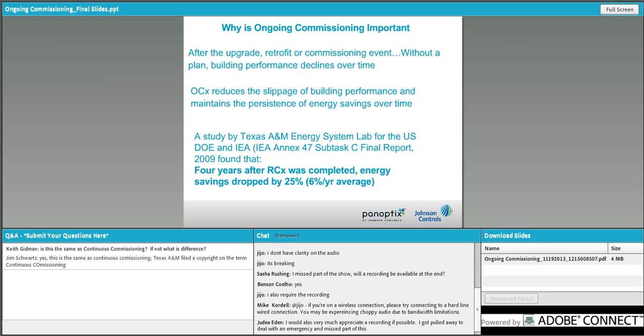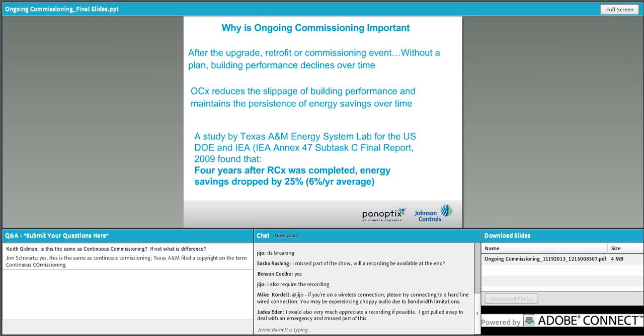And savings slippage doesn't equal 6% every year. You could lose a lot one year. Certain measures, like control changes, are easily changed and modified in the field, and that could generate a large degree of slippage. So ongoing commissioning addresses the challenge of degradation of building performance by ensuring that system performance persists over time and can actually improve.